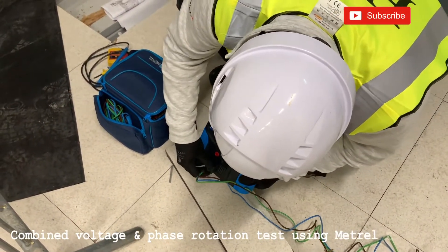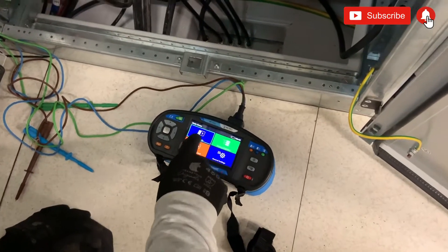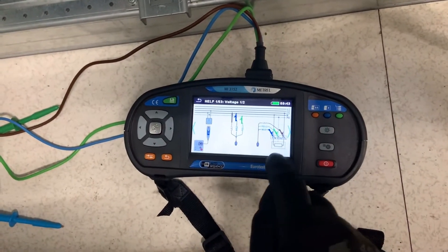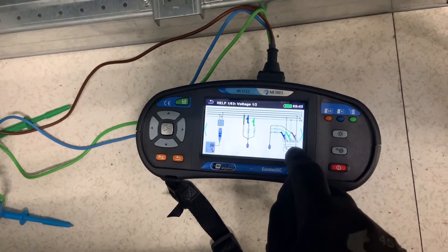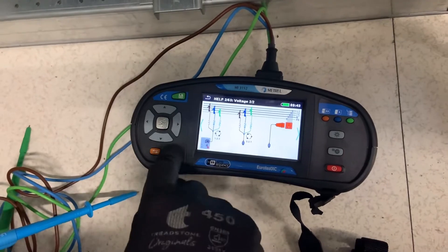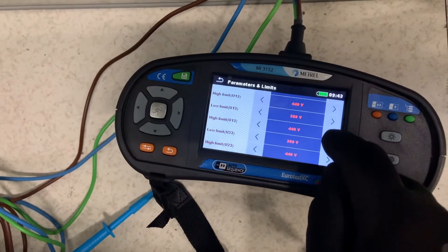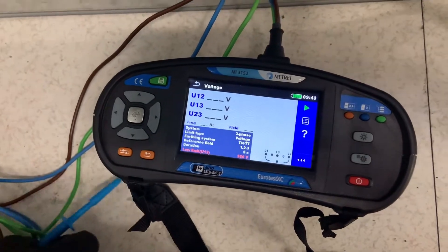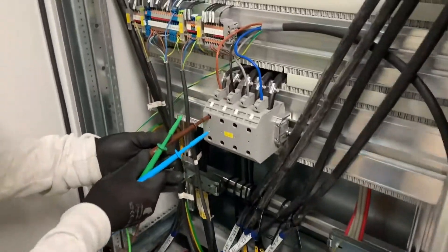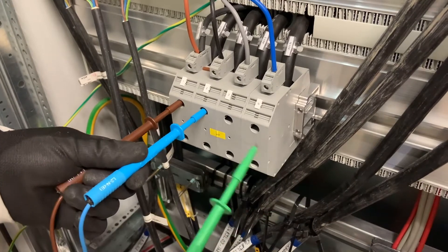So we then moved on to the combined testing using the Metrel unit. For this we select single test, U for voltage. We can touch the help button and it will show you how to connect the meter — this for a single phase, and the following page for a three-phase connection. Happy with the connections, we can now perform the test. We have the options of setting the parameters: whether it's a three-phase test, what kind of earthing system it is, and what the phase sequence should be — in this case one, two, three. The L1 in this case is the brown, L2 is the blue, and finally the green lead on L3.